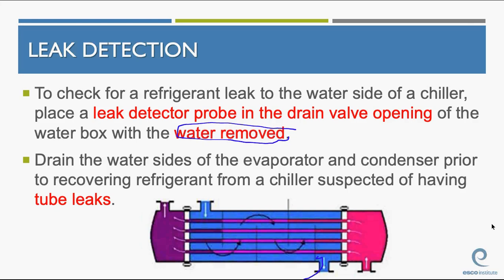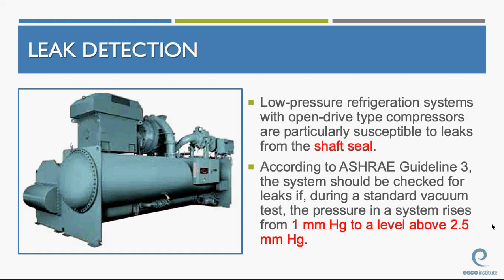Drain the water sides of the evaporator and condenser prior to recovering refrigerant if it has a leak. If you suspect that there's a tube leak, the refrigerant has to be recovered to fix that leak, but you got to drain the water first, because that way your recovery machine doesn't pull water in from the leak. Again, the water pressure is higher than the refrigerant pressure. We don't want to pull water in.